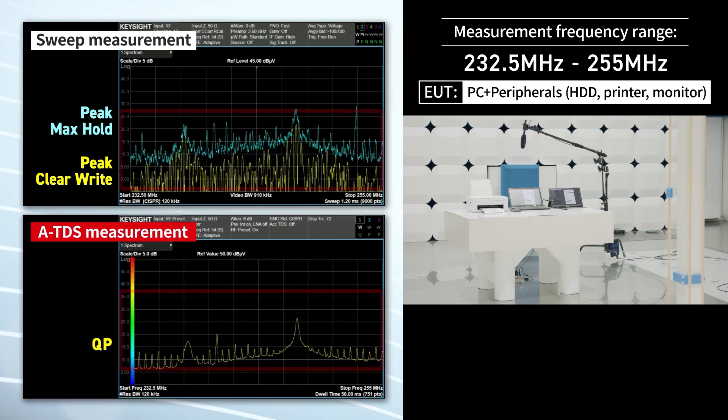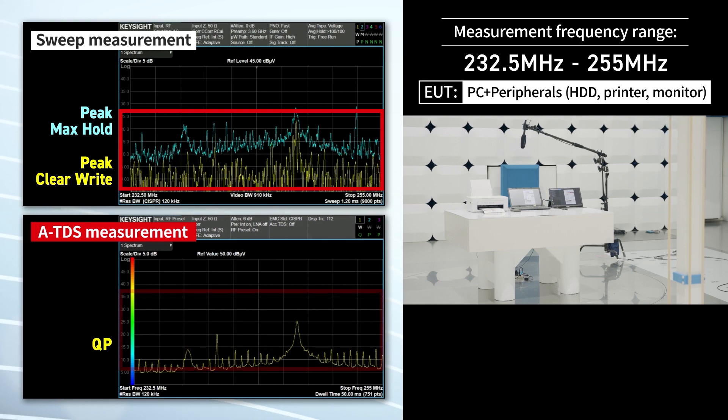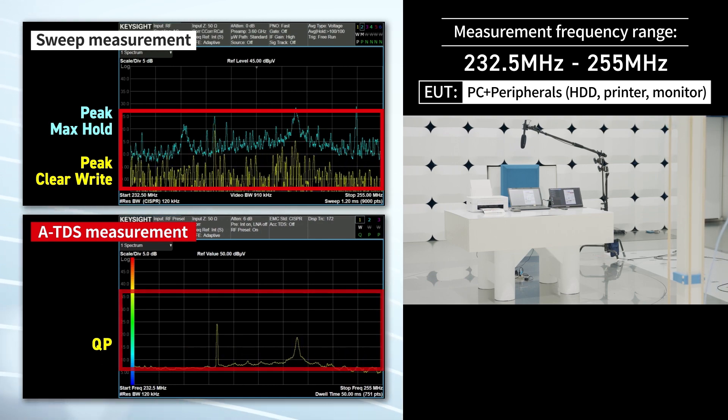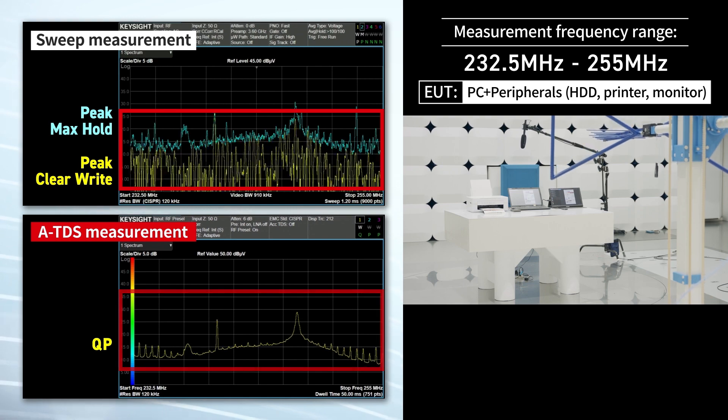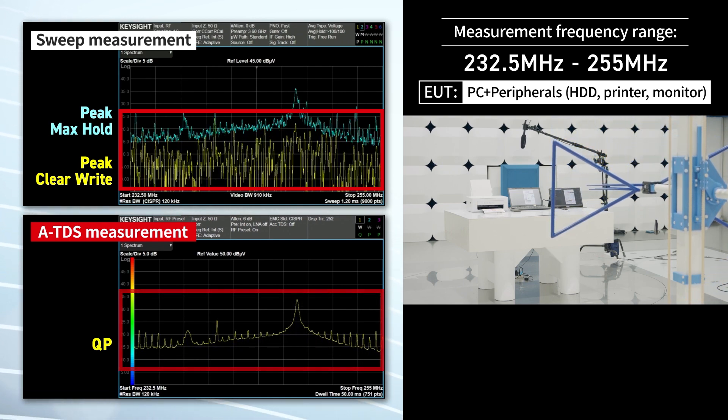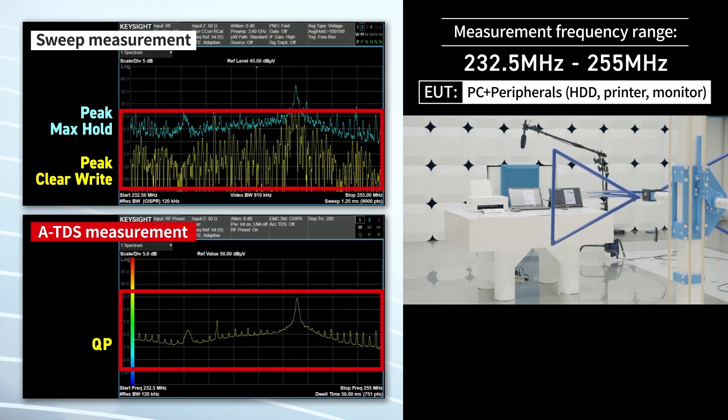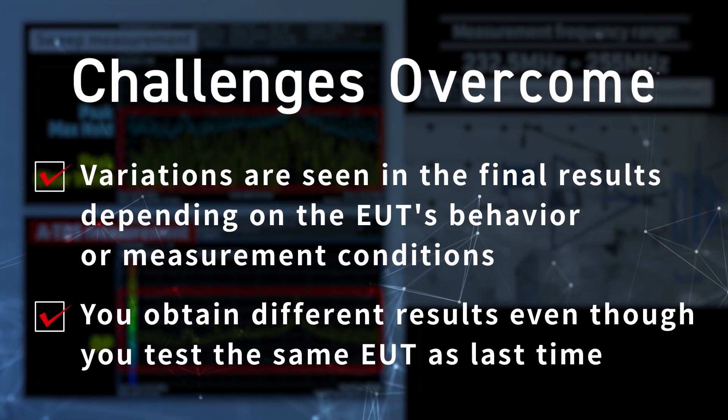With the ATDS feature, you can continuously monitor the noise behavior in a wide bandwidth in the QP mode in the compliance measurement. This is not possible with the conventional EMI receiver mode. This allows you to obtain accurate and repeatable results.